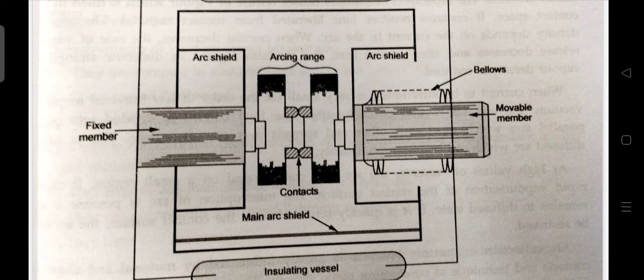However, the arc is quickly extinguished because the metallic vapors, electrons and ions produced during arc rapidly condense on the surface of the circuit breaker contacts resulting in quick recovery of dielectric strength. The salient feature of vacuum as an arc quenching medium is as soon as the arc is produced in vacuum, it is quickly extinguished due to the fast rate of recovery of dielectric strength in vacuum.